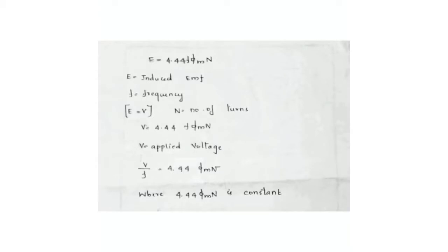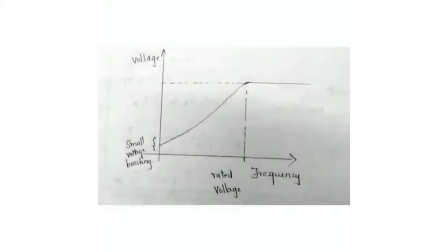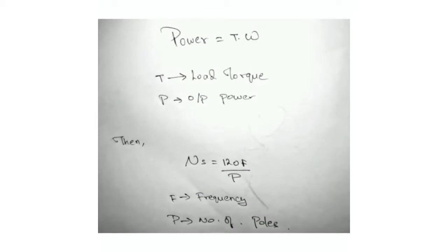Now we are going to plot the curve of voltage against variable frequency. In this curve, as the frequency is increased, we can get the voltage up to the rated voltage, and the rotor speed is given by 120 f by P. So we get the desired frequency f star. The desired frequency f star is converted into omega star by multiplying it with 2 pi. Now omega star is converted into the angle theta star by doing integration.